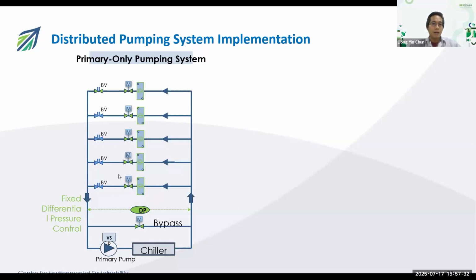And definitely, you need the balancing valve. The reason is that just imagine if all the balancing valves are fully open, definitely most of the water will go to the nearest branch, and there will be less water going to the furthest branch. That's why, before you can control the amount of water into each branch, you need the balancing valve to make sure that there is a balanced flow in each of the branches, and subsequently you can control with the modulating valve.